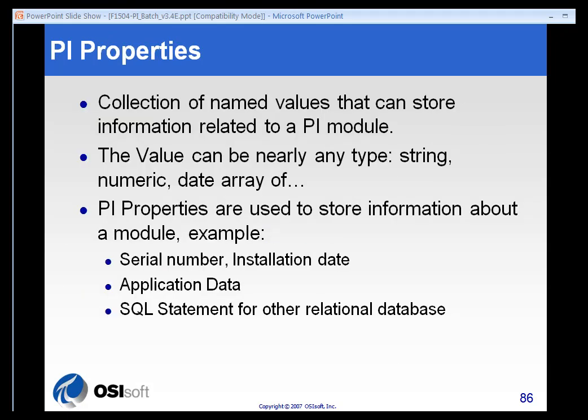Properties are in some ways the opposite of aliases, in that they contain data that doesn't change. PI tags, being process values, inherently change. PI properties are what we sometimes refer to as constants — values that don't change, or if they do change, they change very infrequently. Some examples might be a serial number of a piece of equipment, the installation date, the last maintenance date, specifications like target temperatures, vibration specs, pressure specifications, or safety data — things that may change over time, but generally don't change very often.